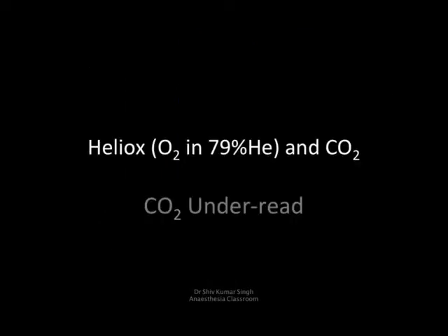Now, if you look at heliox, sometimes used in patients with difficult breathing, which contains 21% oxygen and 79% helium, it also affects the capnography. Capnography is going to underread if you use heliox in these patients and monitor the carbon dioxide levels.